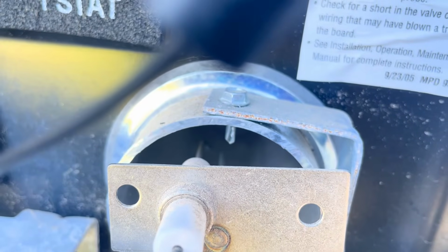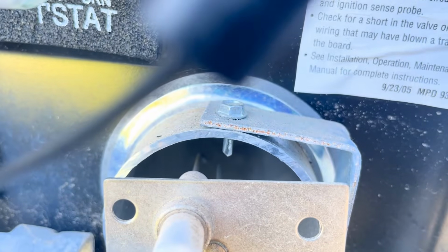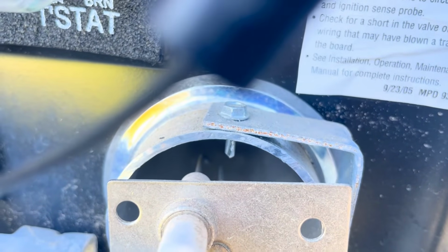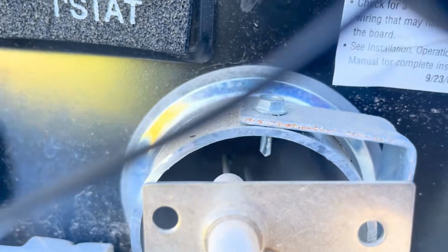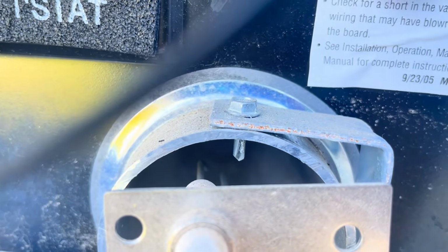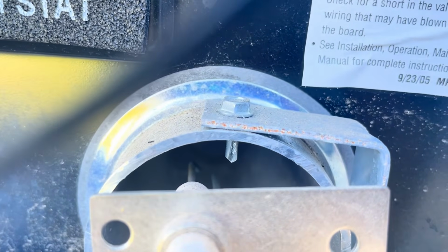If your igniter on the circuit board will arc to the terminal while you hold it close, but when you reconnect it, you do not see a small arc on the igniter that is inside of the tube on your water heater, then there's a chance that that igniter down there is bad. Go ahead and disconnect it and give it a little clean off with an emery cloth, a little bit of sandpaper. Just make sure there isn't some ash or something that's preventing that arc from happening.